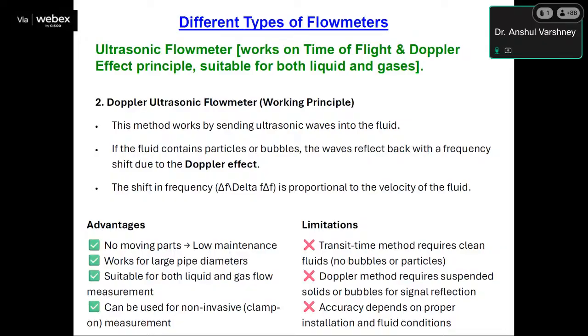The second type is the Doppler type ultrasonic flow meter. This method works by sending ultrasonic waves into the fluid. If the fluid contains particles or bubbles, the waves reflect back with a frequency shift due to the Doppler effect, and that shift in frequency is proportional to the velocity of the fluid. These two types of ultrasonic flow meters are generally used for liquid as well as gas.